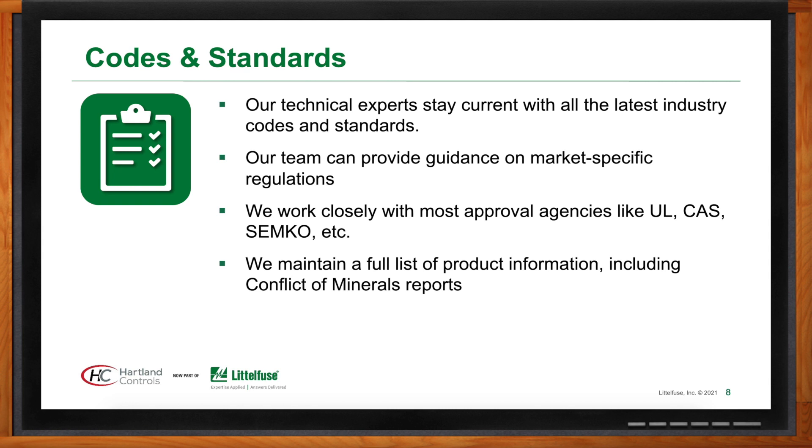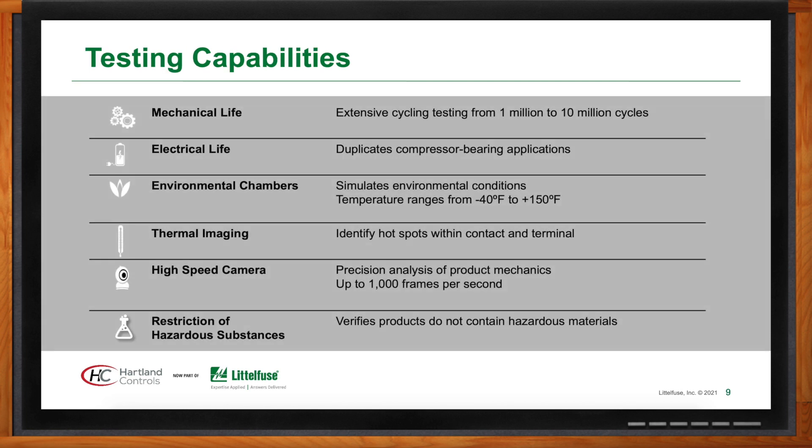Hartland Controls 100% tests their products before they ship from the Shanghai facility. Their engineering lab in Rock Falls, Illinois can test products for mechanical life or electrical life. They have environmental chambers for sub-zero and elevated temperature testing, thermal imaging cameras to detect hot spots and high-resistance joints in electrical connections, and high-speed cameras to dissect mechanical devices. For example, they can cut a contactor in half and film the contacts to look for contact bounce, which would create excess arcing.